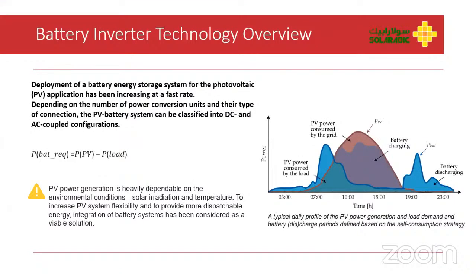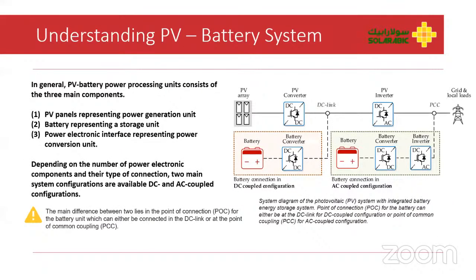The integration of the battery systems has been considered as a most viable solution. So considering the integration of the battery systems to a photovoltaic system and their point of connection, it is classified into two configurations, the DC coupled configuration and the AC coupled configuration. In general, any PV battery system has majorly three main components: the PV panels representing the power generation unit, the battery representing the storage unit, and the power conversion electronic units, for example, inverters, converters, and the battery inverter. Depending upon the configuration and the connection of these components, we can derive two configurations of it, the DC coupled configuration and the AC coupled configuration.